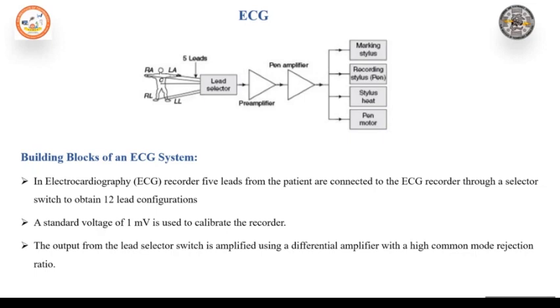The frequency selective network is an RC network that provides necessary damping of the pen motor and is preset by the manufacturer. The auxiliary circuits provide a 1 millivolt calibration signal and automatic blocking of the amplifier during a change in the position of the lead selector switch. It may include a speed control circuit for the chart drive motor.